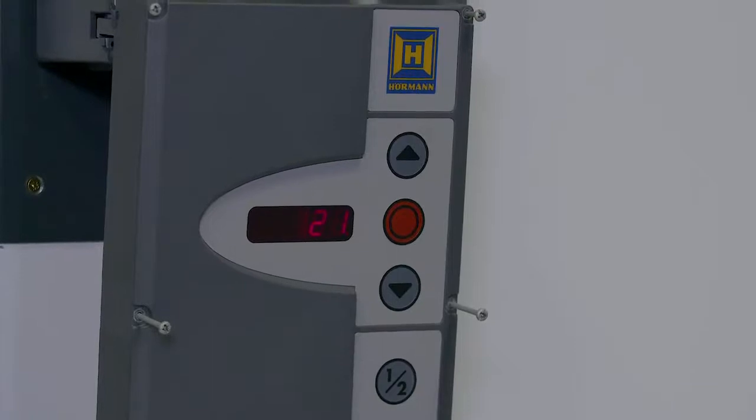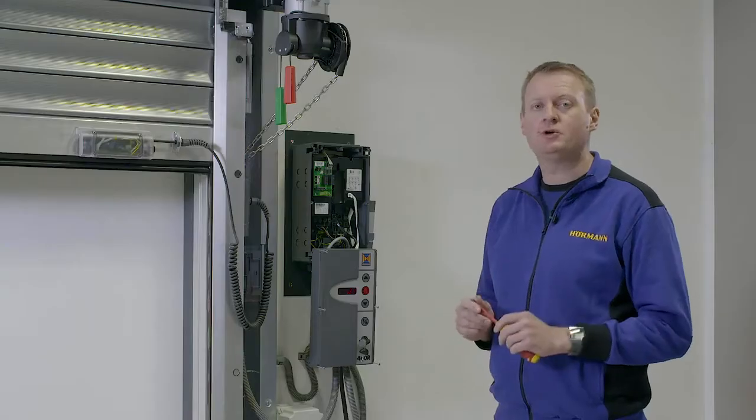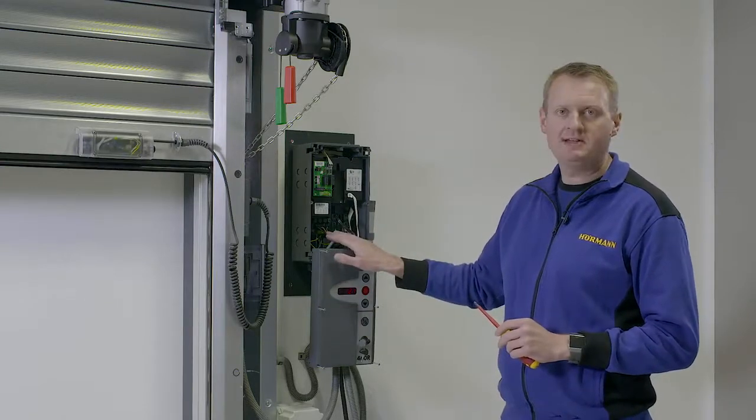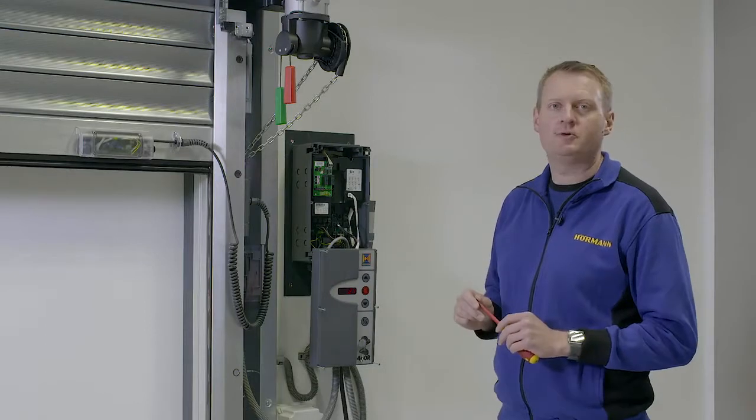Error code 21 says that the motor is physically blocked. This is usually caused by a missing phase. Please check the incoming phases and the 10 amp fuses on the control card.